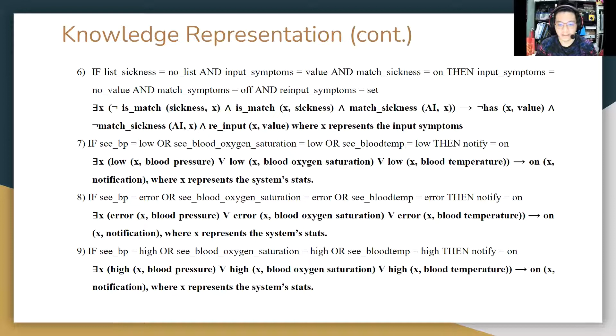Number 8 is if the blood pressure error or blood oxygen saturation error or blood temperature error, then notify is on. This shows that there is an error inside the machine to look at all this data. So this will notify the staff to look at the machine and change it if necessary. Number 9 is if the blood pressure, blood oxygen saturation or blood temperature is high, it will also notify the staff because the patient needs medical attention immediately.